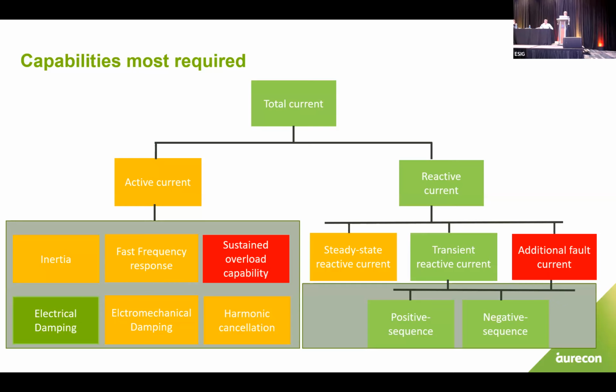By color coding here, I mean those highlighted in red are least required or desired, and those highlighted in green are most required. Part of this comes with the important recognition that you cannot realistically get all these capabilities or services from the same device, same project, simultaneously. That's simply impossible - it's going to exceed the capability of a grid forming inverter, and that's not control capability, it's the current rating.